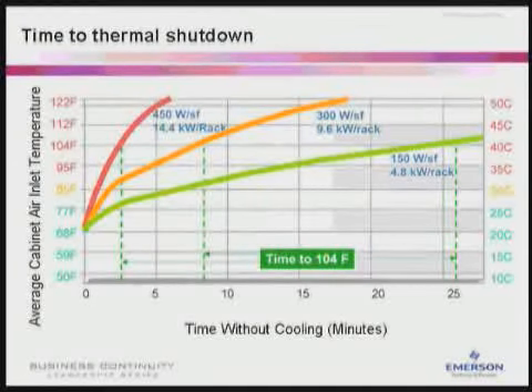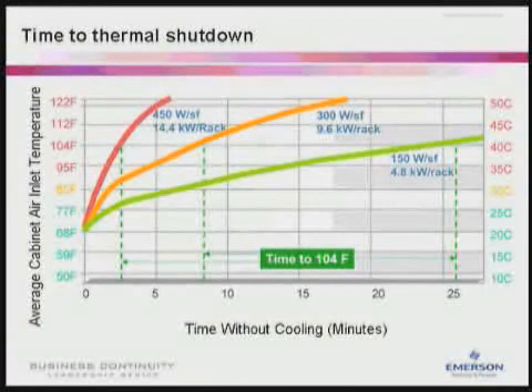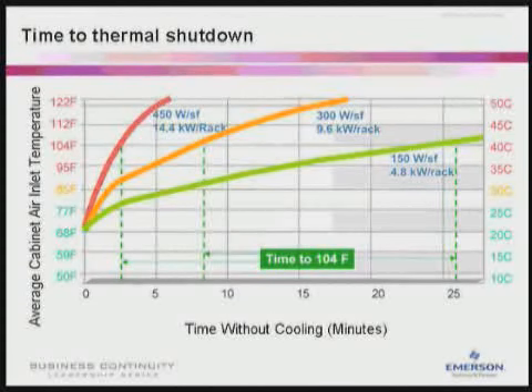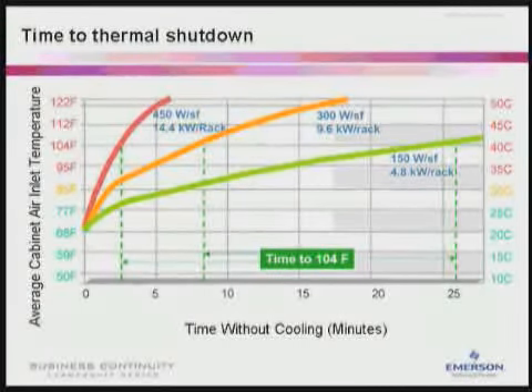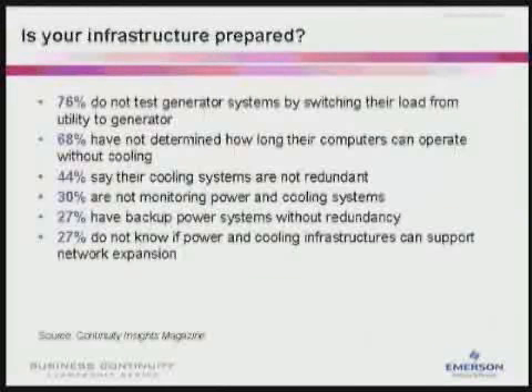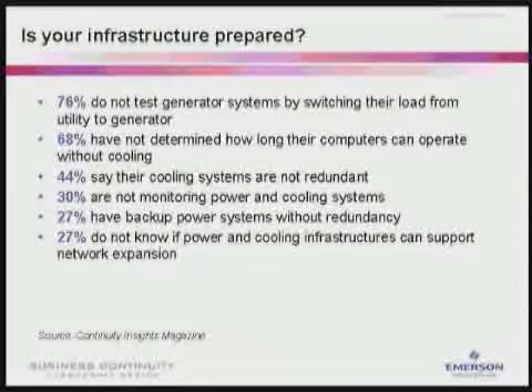So in just 4 hours, the telecom equipment overheated and failed. On the power side, they actually had enough generator runtime to ride through the 8 hours. So the cooling issues cut their planned ride-through in half. As densities increase, more organizations will experience these types of outages if they don't take preventive measures.